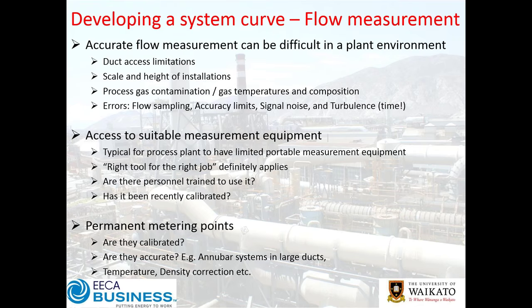Turbulence is going to be present all the time. Typically these flows are statistically steady but instantaneously turbulent or unsteady. Taking a reading averaged over 2–3 minutes can become important to get a fair and representative result. Access to equipment is important — it's definitely a case of the right tool for the right job. Are your people trained to use the equipment? Has it been calibrated? When was it last checked after being dropped?